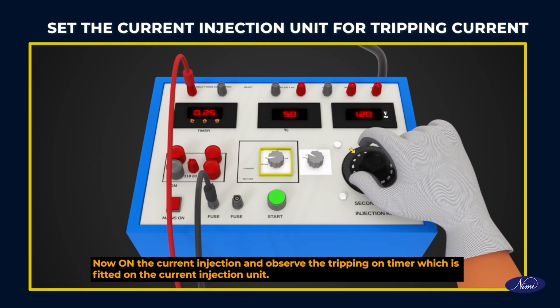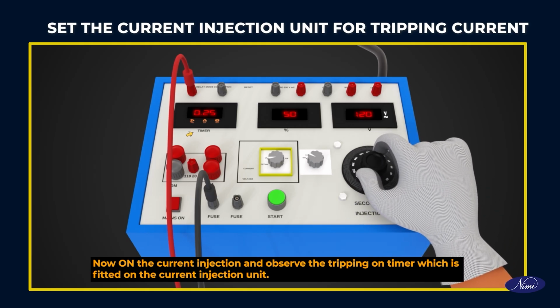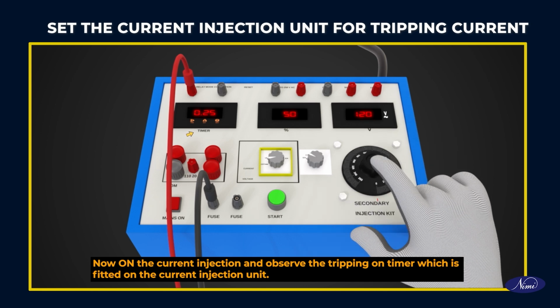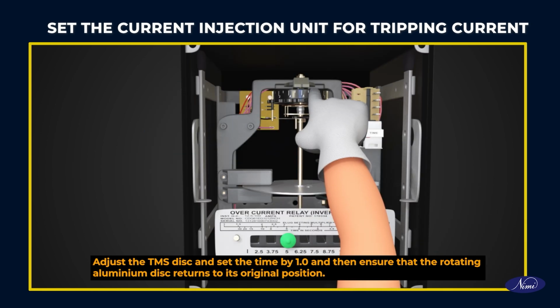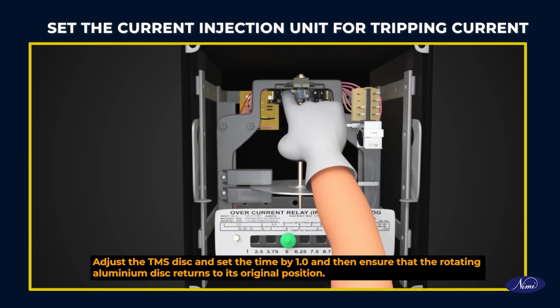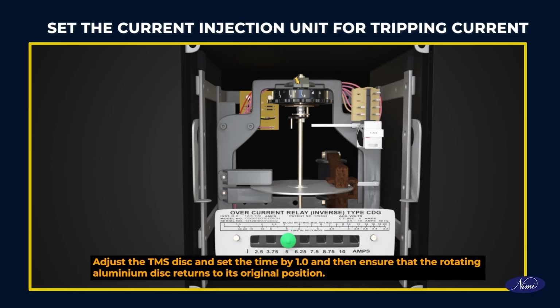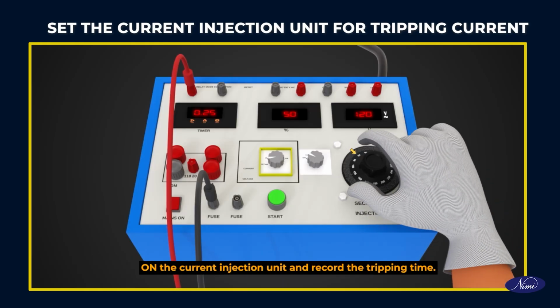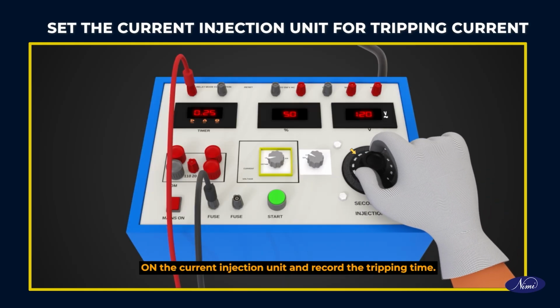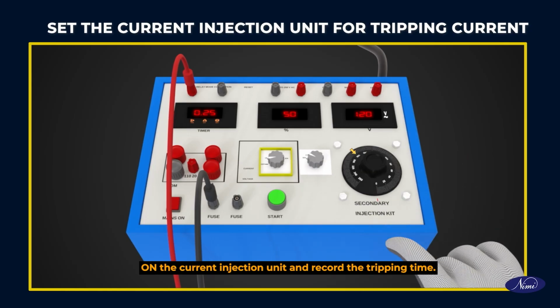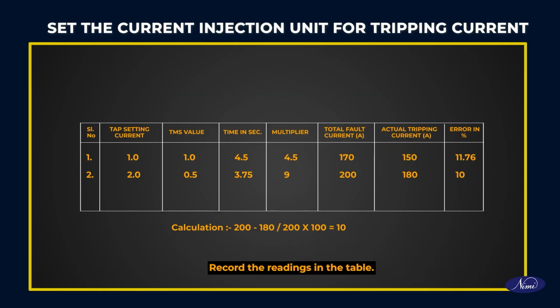Now, on the current injection unit and observe the tripping on timer which is fitted on the current injection unit. Adjust the TMS disc and set the time to 1.0 and then ensure that the rotating aluminium disc returns to its original position. On the current injection unit, record the tripping time. Record the readings in the table.